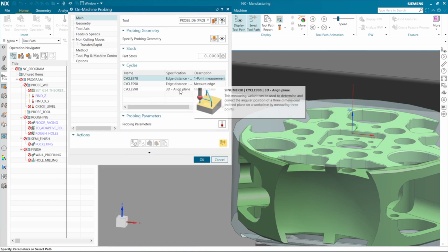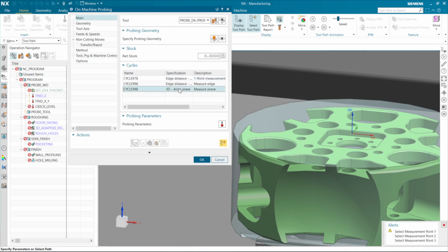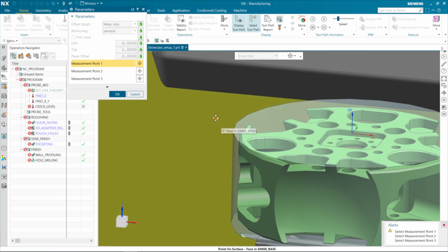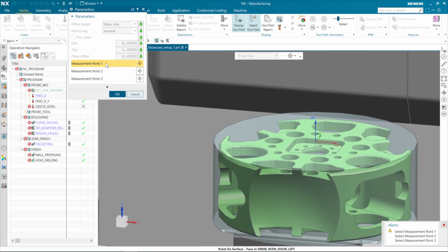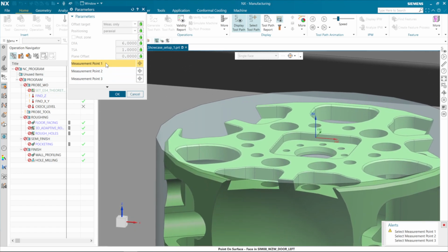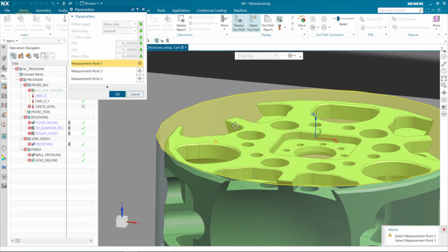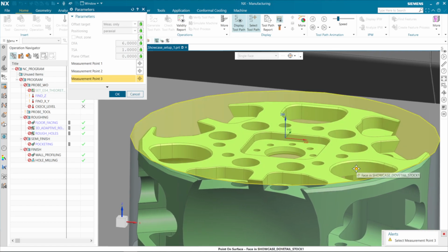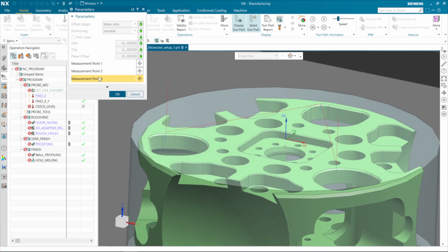And we're going to select our 3D align plane. This can be used to determine and correct the angular position of a three-dimensional inclined plane. You see in the corner we have a couple of alerts that already come up saying to select all these measurement points, and that's in our probing parameters. We can clear these alerts fairly quickly by specifying some points. I'm going to select 3 points on the face here. You cannot automatically cycle through these. You have to select each one. And I'm going to select the last measuring point. There we go. You can see a preview of our toolpath already.